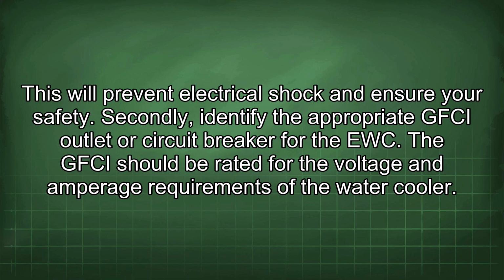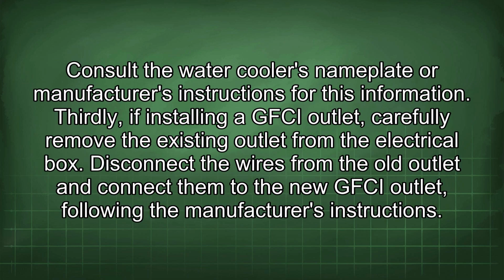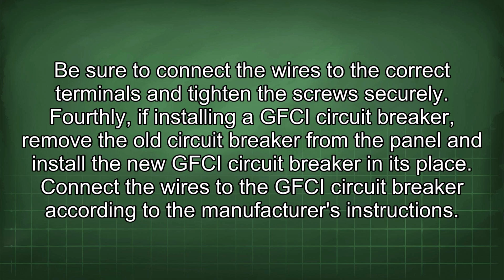Secondly, identify the appropriate GFCI outlet or circuit breaker for the EWC. The GFCI should be rated for the voltage and amperage requirements of the water cooler. Consult the water cooler's nameplate or manufacturer's instructions for this information. Thirdly, if installing a GFCI outlet, carefully remove the existing outlet from the electrical box. Disconnect the wires from the old outlet and connect them to the new GFCI outlet following the manufacturer's instructions. Be sure to connect the wires to the correct terminals and tighten the screws securely.